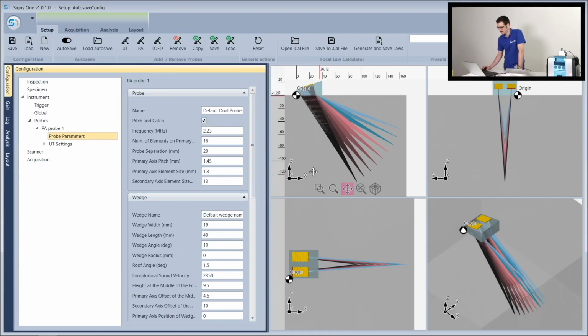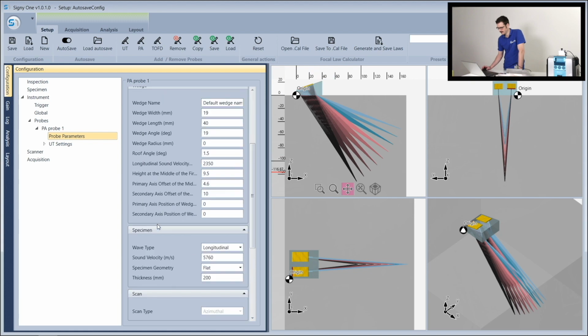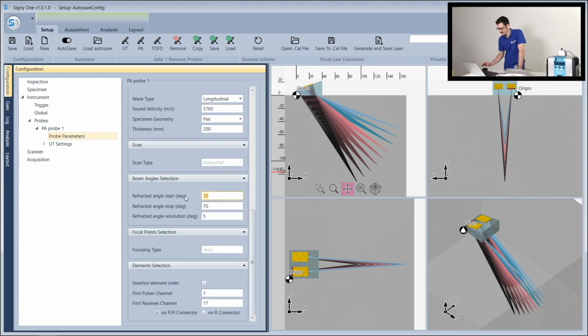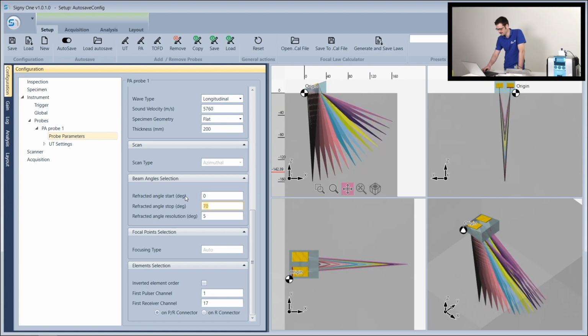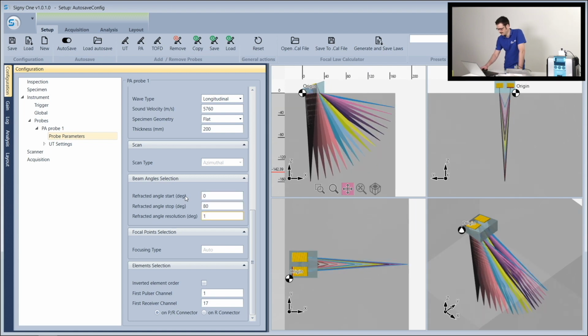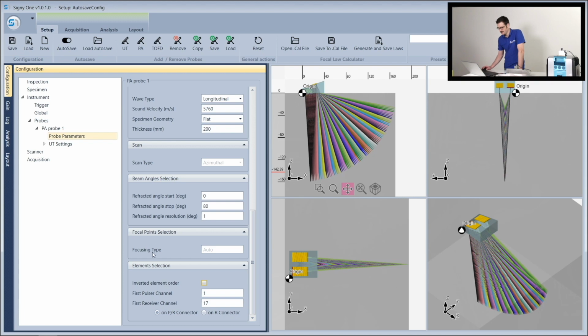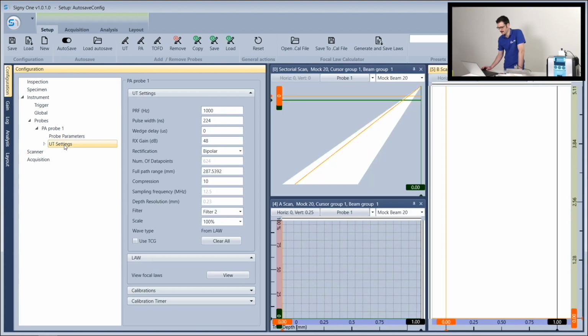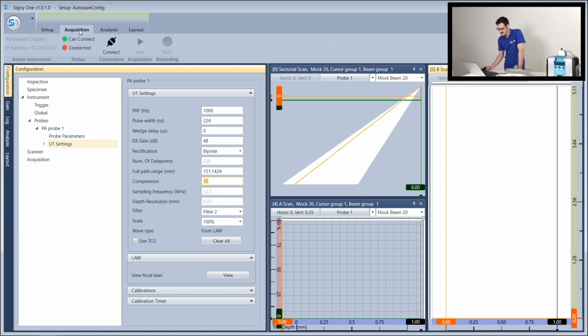The geometry of the probe has been loaded, and I will scan from a refracted angle from 0 to 80 degrees every 1 degree. The focusing is done automatically based on the geometry of this probe. The focal laws are now updated on the probe, and I will be able to calibrate it for this inspection. I will update the probe range and I will start acquisition.